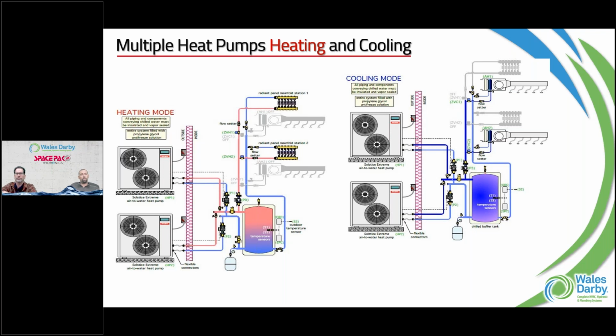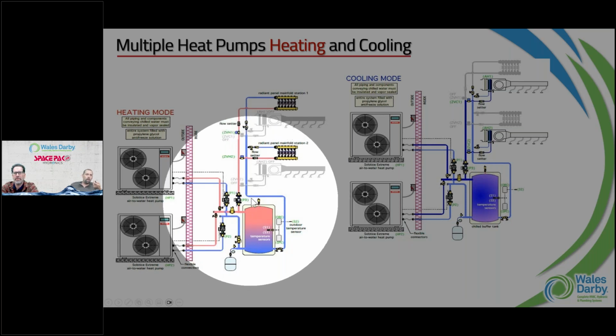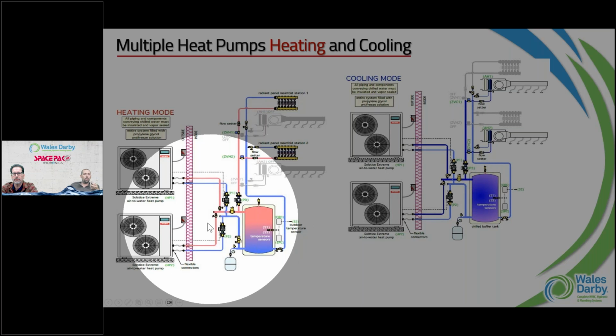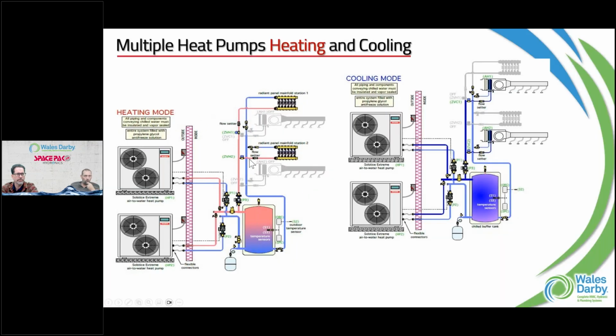And if you pay attention to the piping of the buffer tank, this is a three pipe setup. So there are some benefits there, where with a 3 pipe I'm getting the hottest water out of the tank, but I could potentially be getting, if the heat pumps are on, the hottest water coming directly out of the heat pump, and then up to that radiant floor. So there are different ways of piping it, 3 pipe versus 4 pipe.